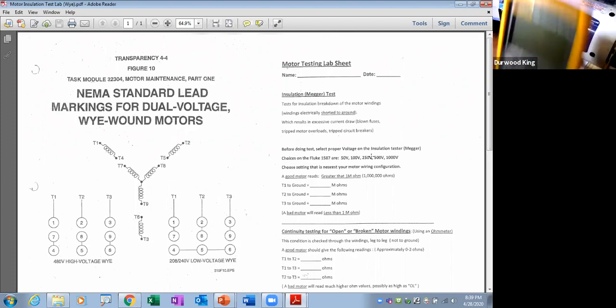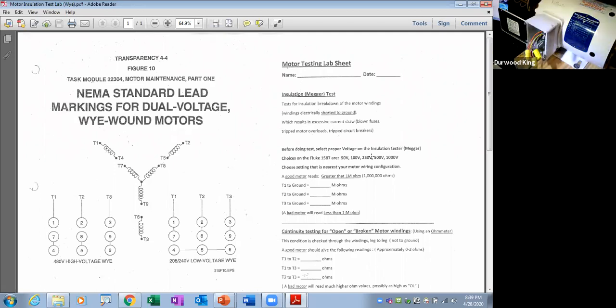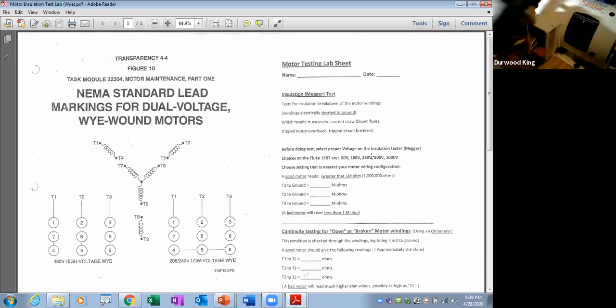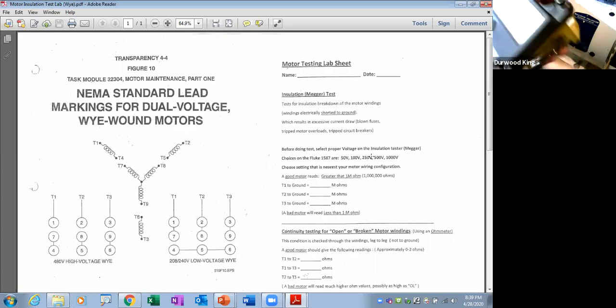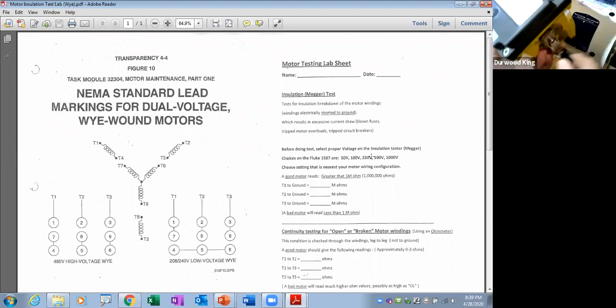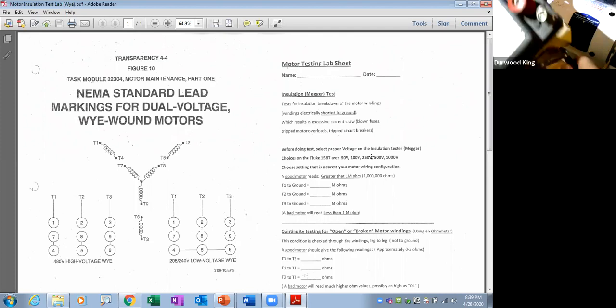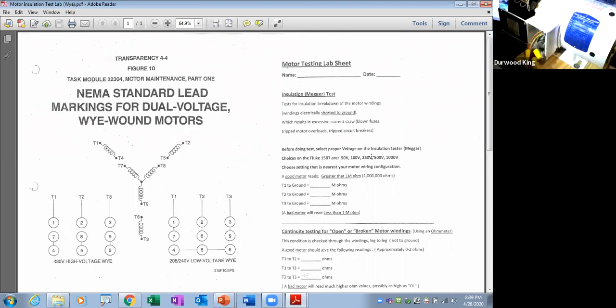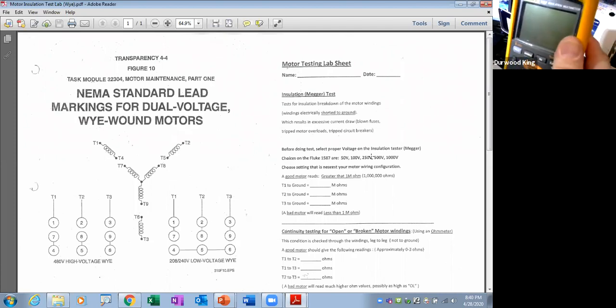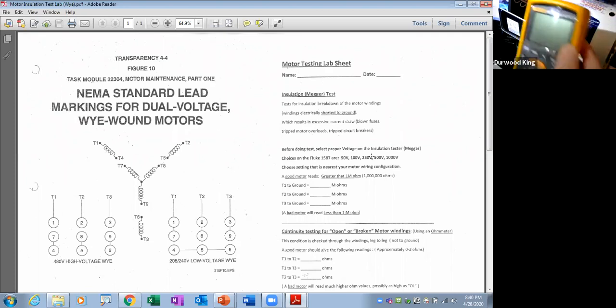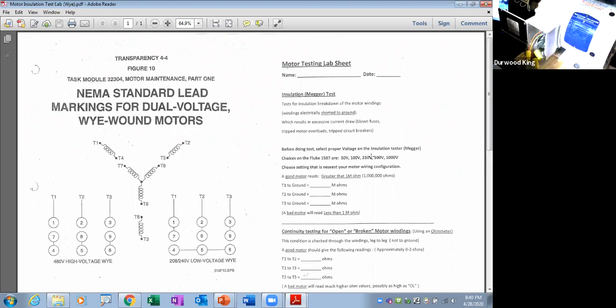So this is a more modern version, and the older one is a crank type. I'll get it out. So the older one is like this, and it has a crank on the side. You see that crank? Yeah. The older one, you actually have to wind it up like that, and it's going to generate voltage. It's going to shoot voltage into the motor, and it's going to detect if you have bad windings in there, or if they are shorted out. If you're interested in learning how to do this one, I'll show you. If not, we'll stick with this. I'm going to let you tell me, okay? This is what most people are using nowadays, but if you want to take a look at the old style, you just say the word and I'll show you, okay? We'll let that be your call, okay?